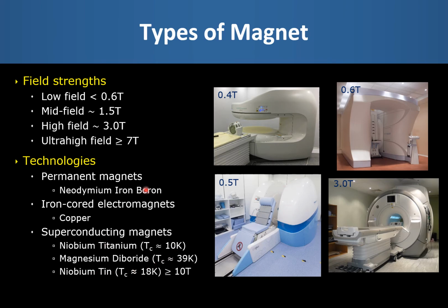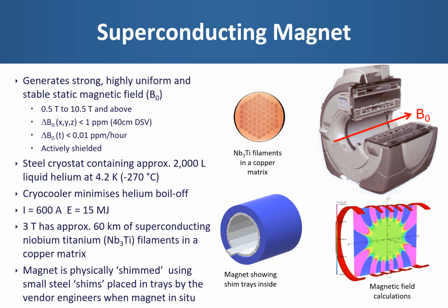For field strengths above about 10 Tesla, it's necessary to move to different types of superconductor made, for example, from alloys of niobium and tin. If we look in a little bit more detail at a superconducting magnet, this is the only way to generate relatively strong magnetic fields above about 0.05 Tesla. And as already discussed, they range from around 0.5 Tesla to 10.5 Tesla and above for research.